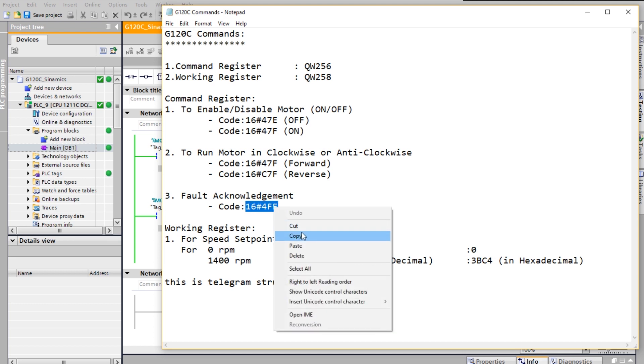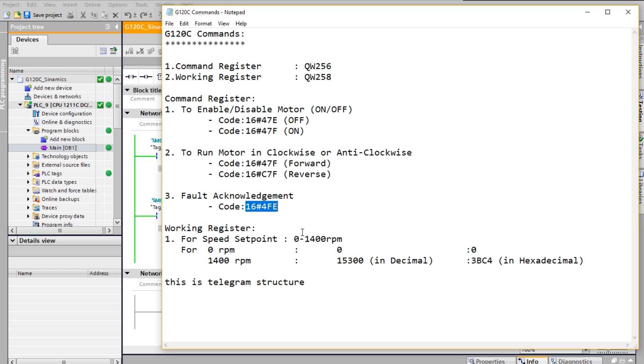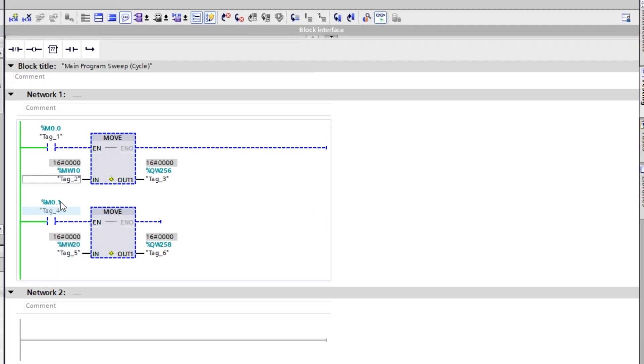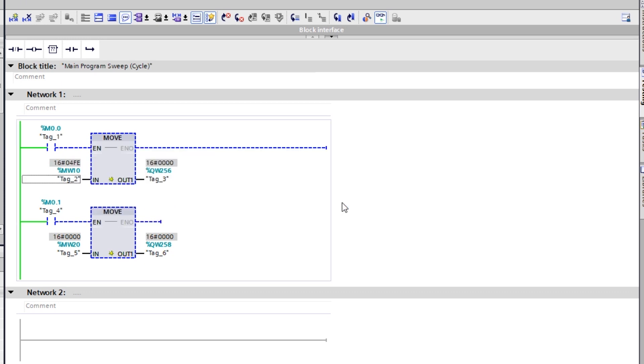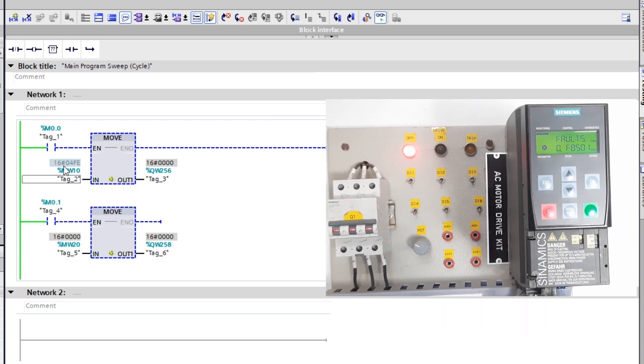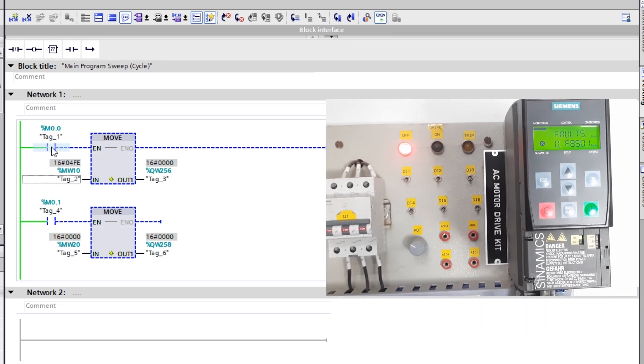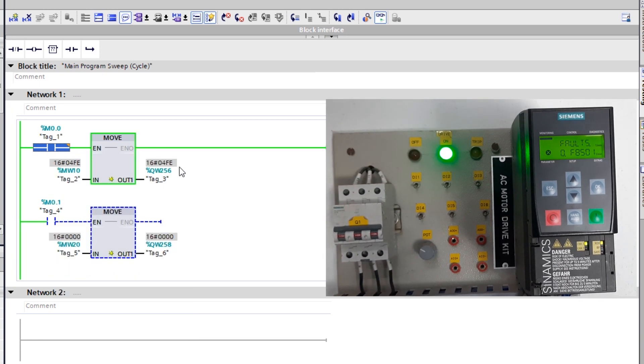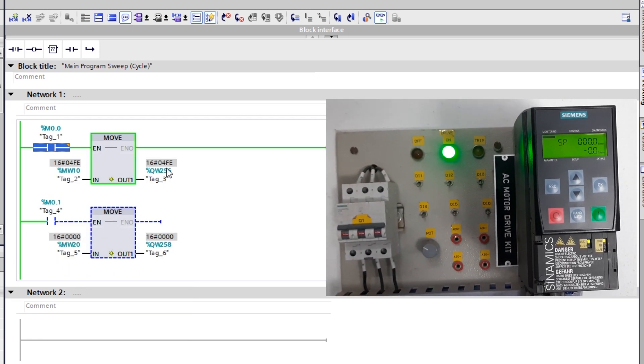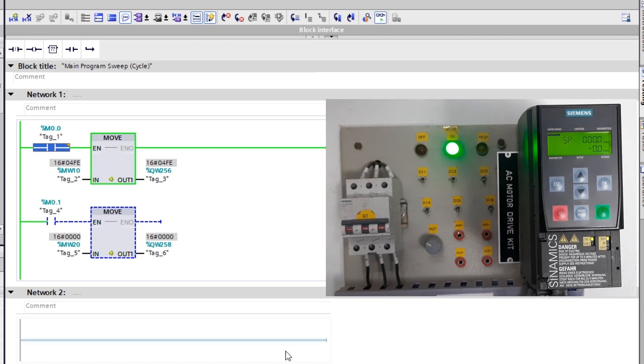First, if there is any fault, you need to acknowledge it using this hex code. I'm going to copy this hex code and load it into the control word register. I'm pasting it into the control word register, and the moment I select this memory bit and modify it to 1, you can see the data is transferred and the fault acknowledgement is cleared.